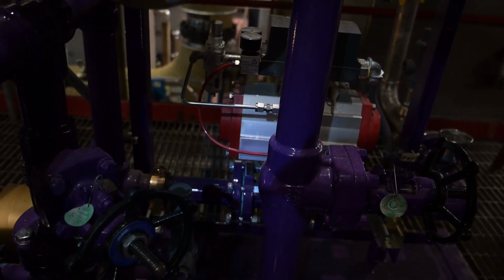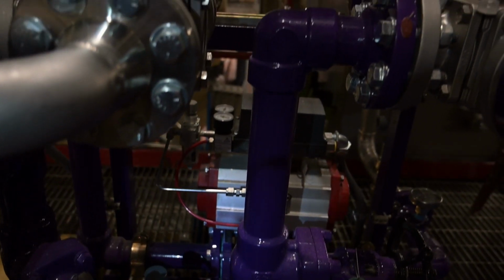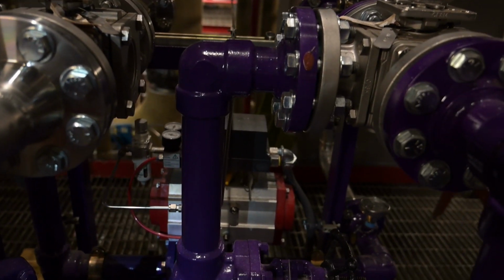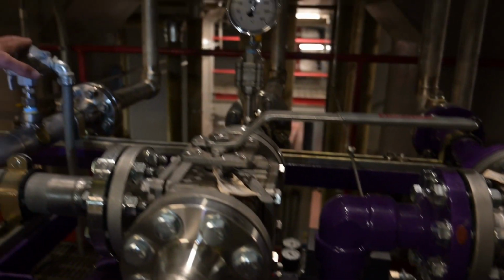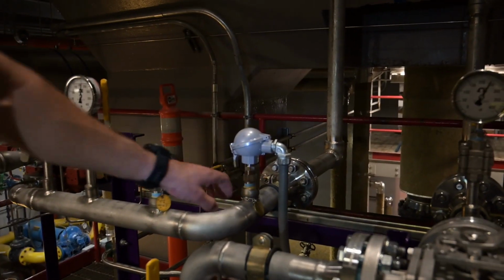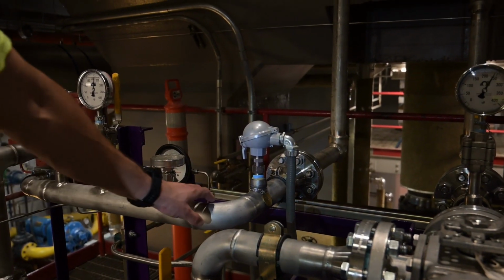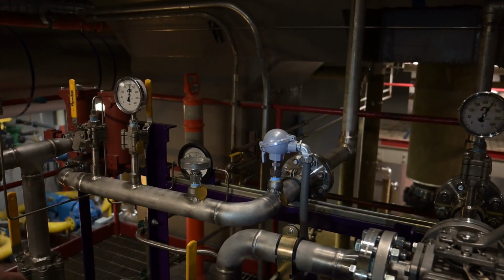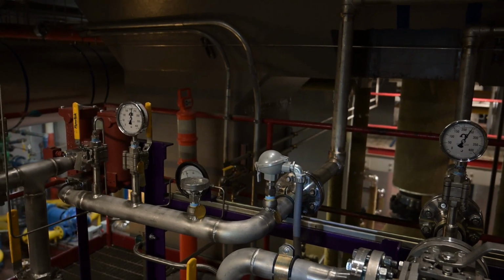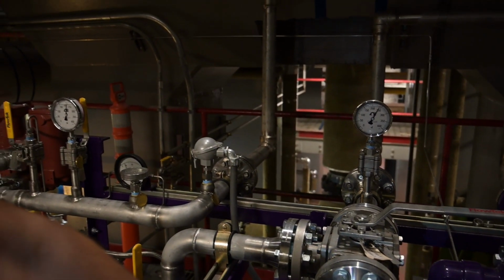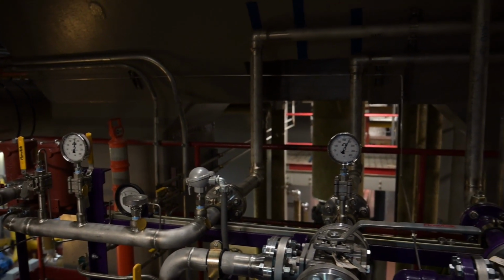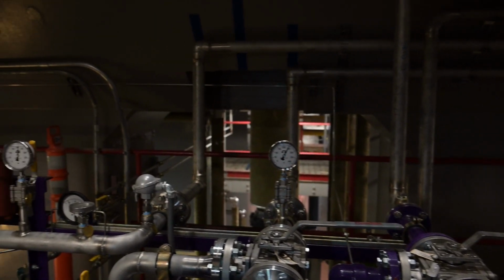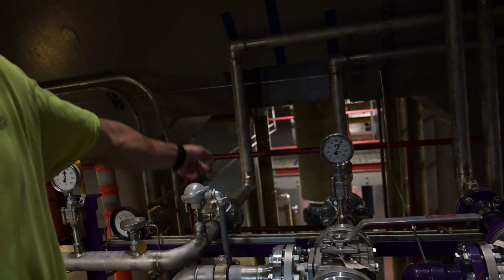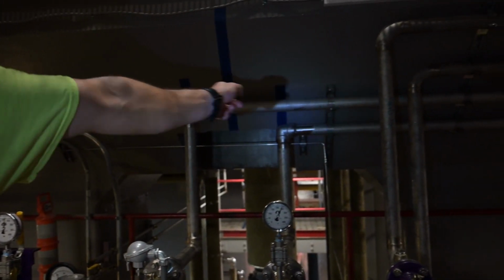This is going to be controlling cooling water flow through the heat exchangers, and it's controlled in a loop off of this RTD temperature. Our set point is going to be 113 degrees Fahrenheit, where we want to maintain the water. So in order to maintain that, the temperature control valve is going to open or close. Okay, so that is lube oil going back to the turbine.